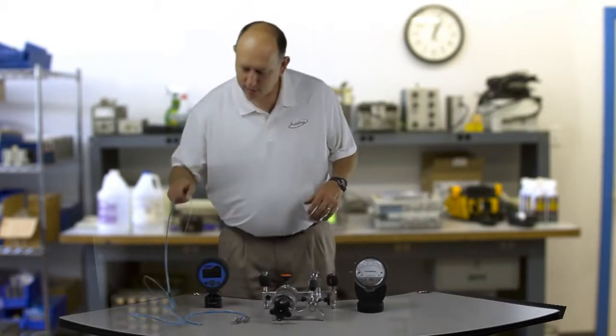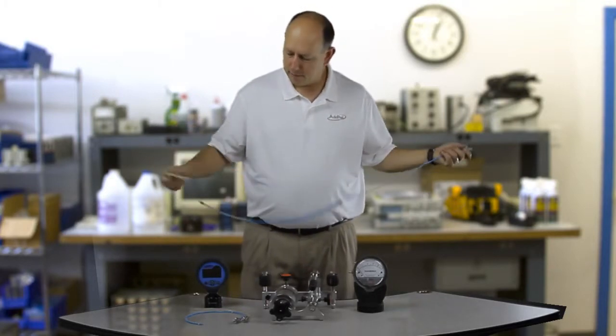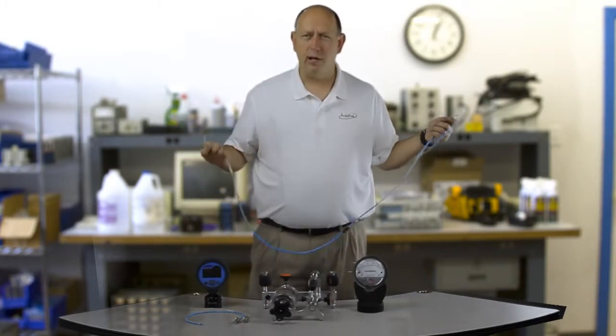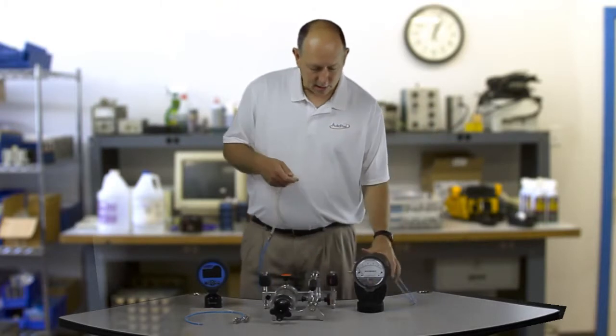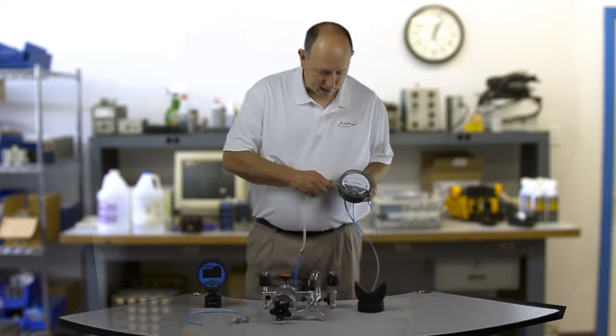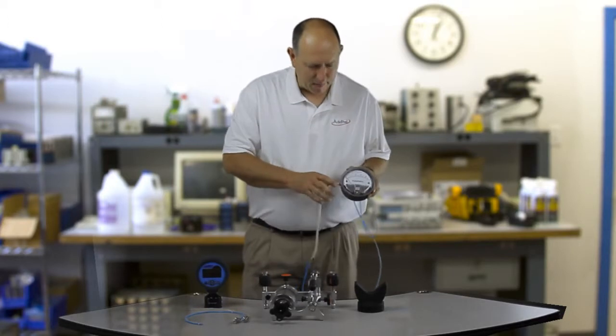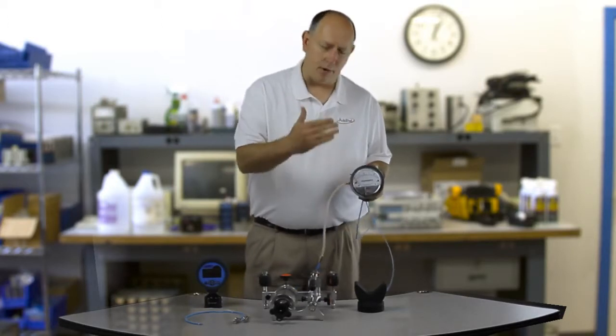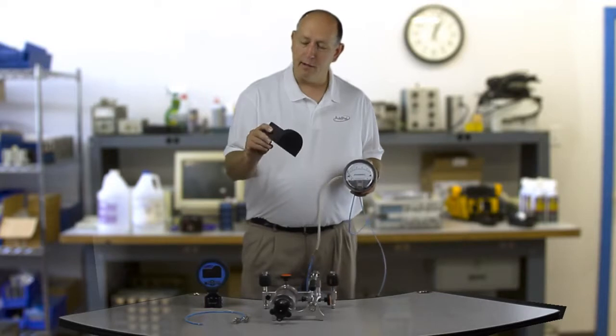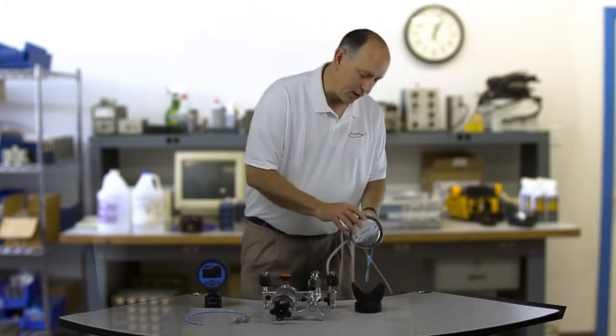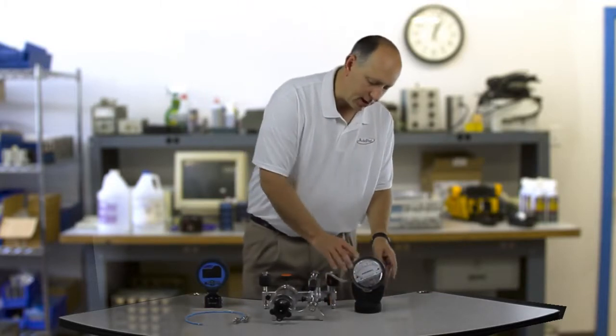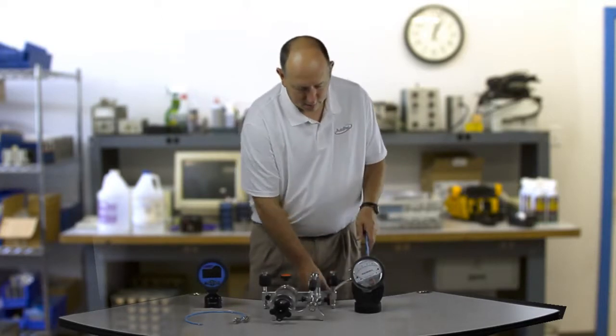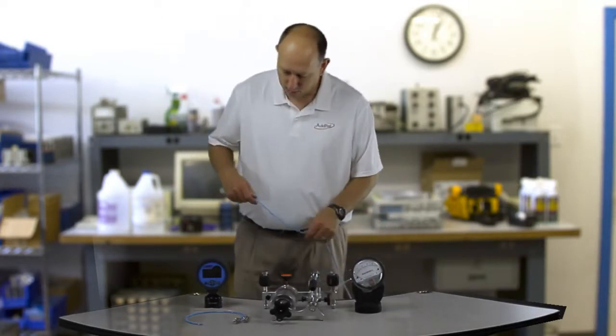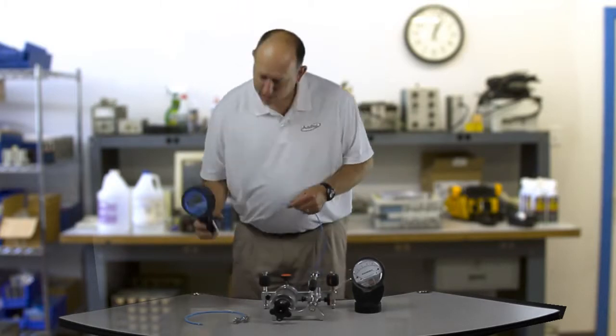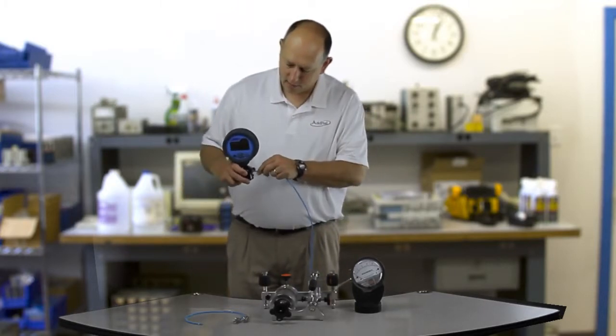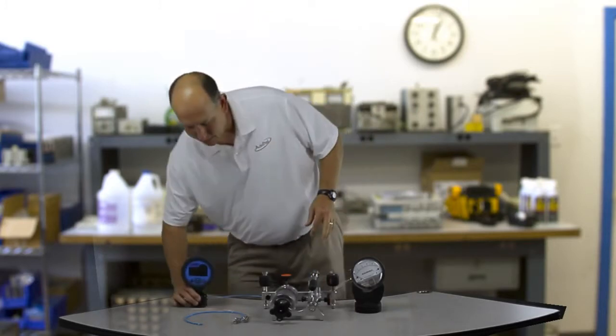How I'm going to start is by tying the low end of the reference and the unit under test together. I'll go into the low end side of the Magnehelic here, and by the way, Magnehelics need to be calibrated in the upright position. That's why I have this little Pac-Man looking tool here, which we actually make and include with this kit. I'll put that on the low side of the Magnehelic and tie it into the low side of the reference gauge, so those two low sides are now tied together.